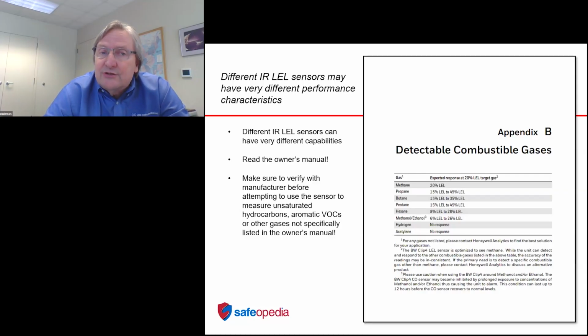Different IR-LEL sensors have very different performance characteristics. You should talk to the manufacturer or read the manual of whatever instrument you're considering if you intend to utilize an IR-LEL sensor. Make sure it does the job. There are some IR-LEL sensors that are great for methane, but they're not very good for aromatics or unsaturated hydrocarbons like cumene or toluene or other VOCs. So you do have to be careful about that.